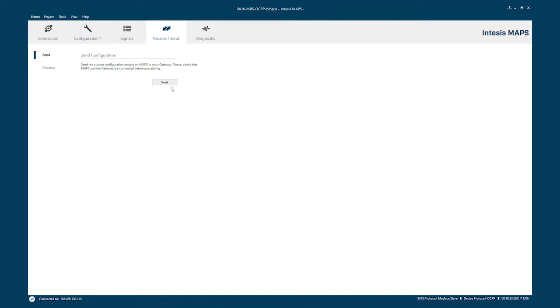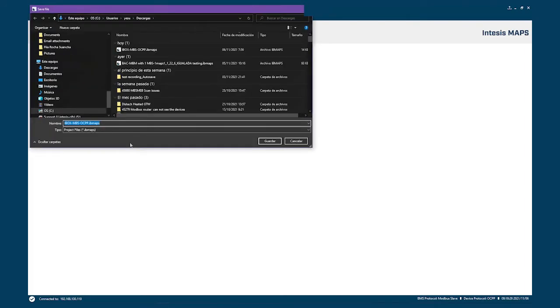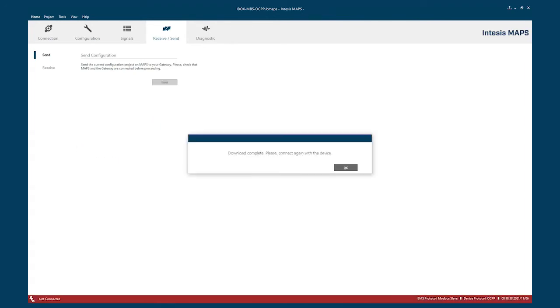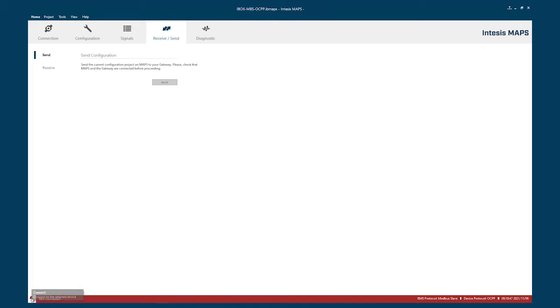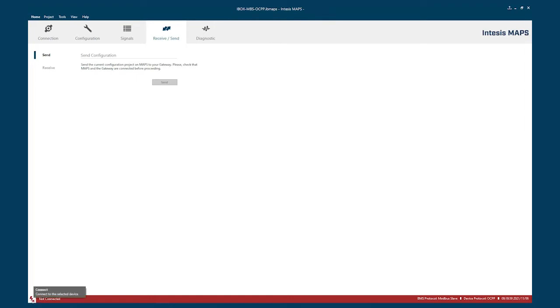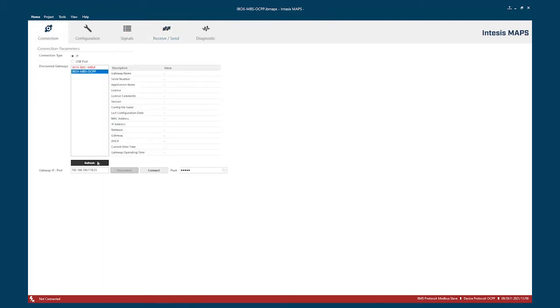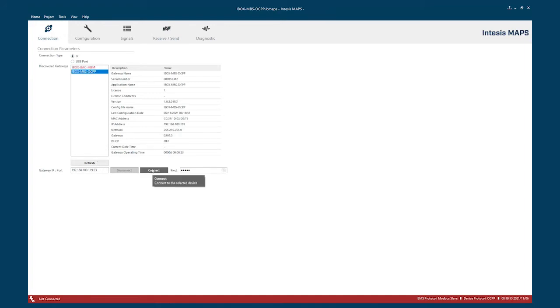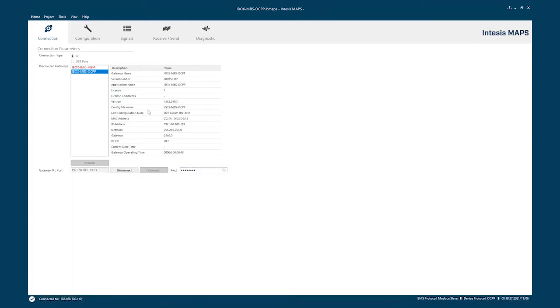And you still haven't sent. So your little star is still here. And you hit send. It's going to ask you to save it. I have an already existing file, so I'm just going to override that. Once it has downloaded to the gateway, it disconnects. So it asks you to reconnect. You can use two methods. You can either hit this little thunder symbol here. But it will need to wait until the gateway reboots after the download. So it's still not rebooting. The other option is to come back to connection and refresh. Once it's already again there, then you can send it. I'm going to need to adjust my password, because it's no longer the default.